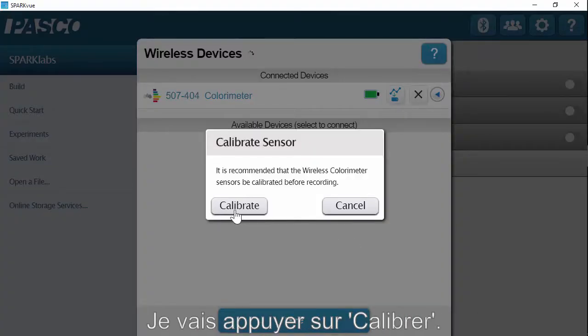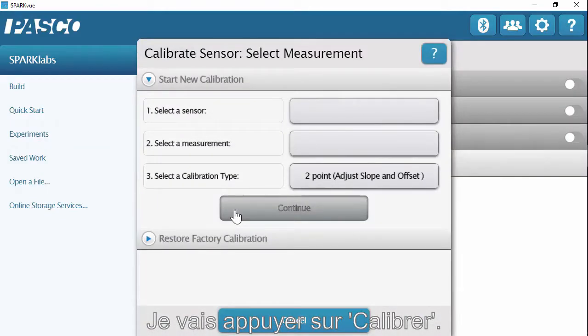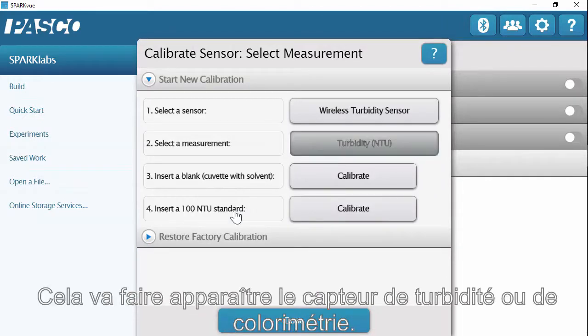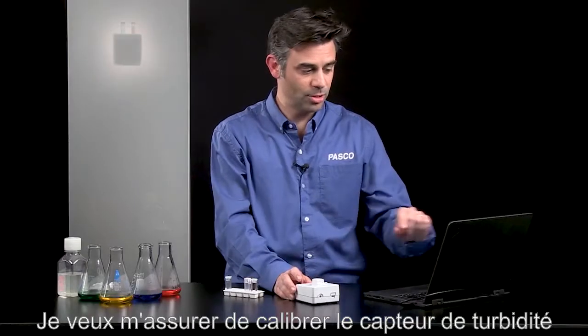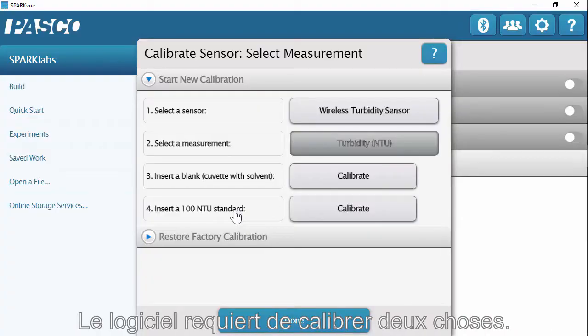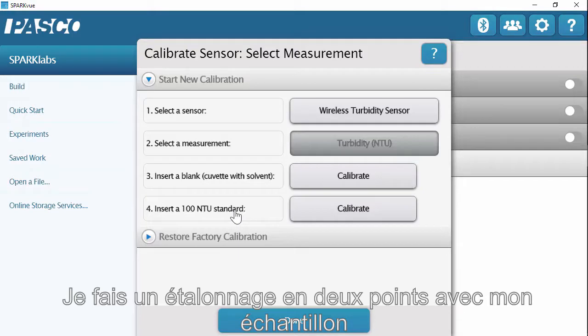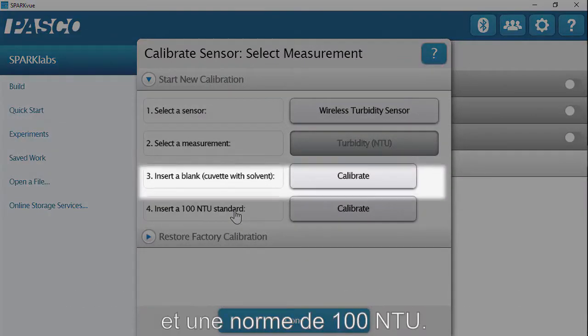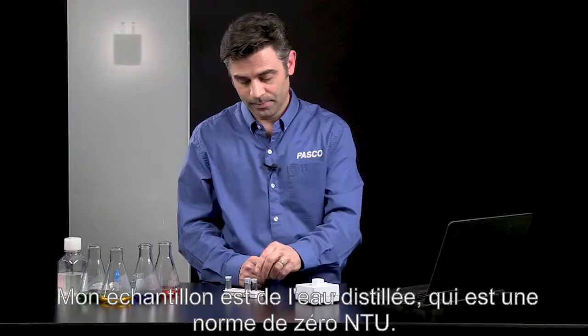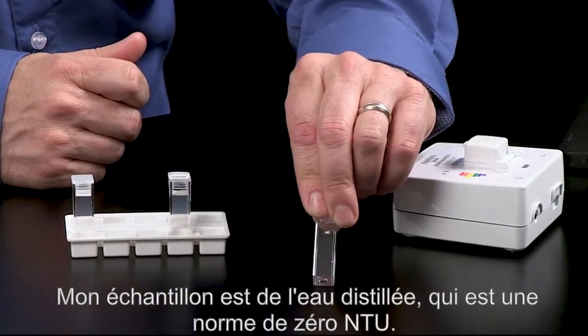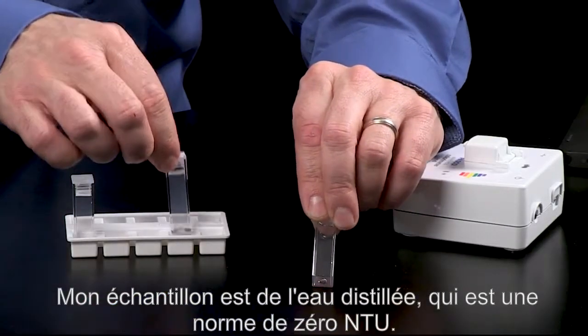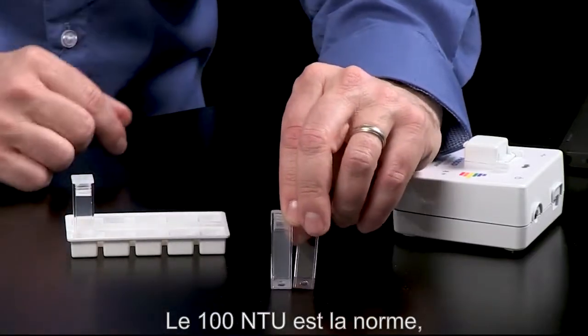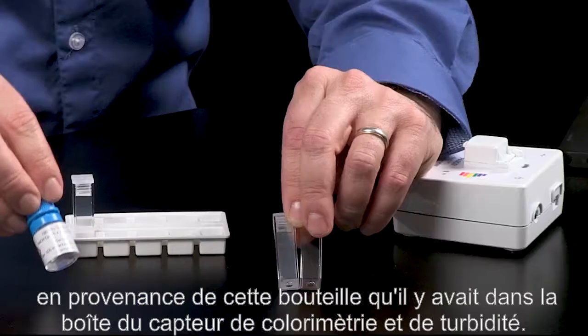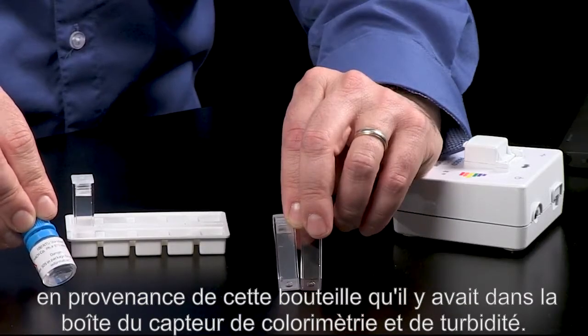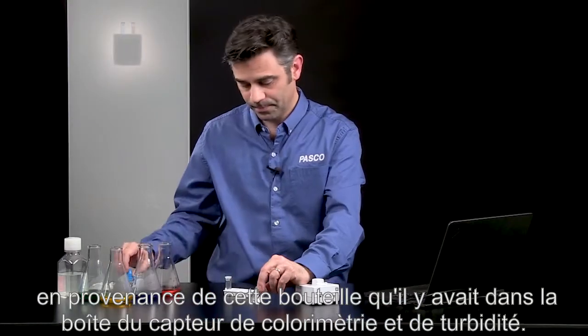I'm going to go in. Since I'm prompted, I'm going to hit calibrate. It is going to pop up the turbidity sensor or colorimeter. I want to make sure I'm calibrating with the turbidity sensor. And now it's going to ask me to calibrate with two things. I'm doing a 2-point calibration with my blank and a 100 NTU standard. So my blank is distilled water, which is a 0 NTU standard. And this is my 100 NTU standard. And that came from this bottle from the colorimeter and turbidity sensor box.